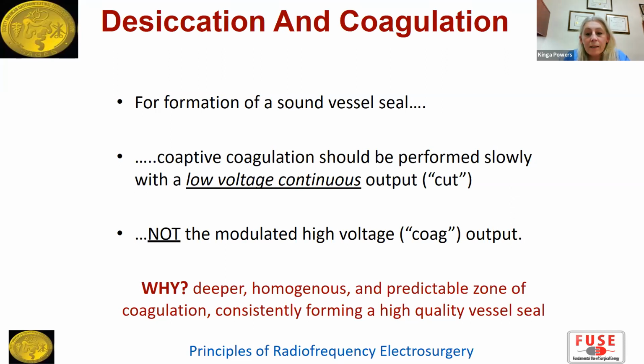Whereas with coag, it's not predictable and it's variable. You may seal a vessel, you may not—it doesn't work as well. Most bipolar devices use the continuous low voltage cut mode to seal vessels.